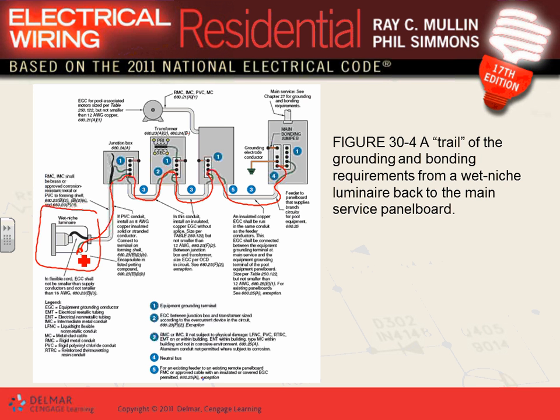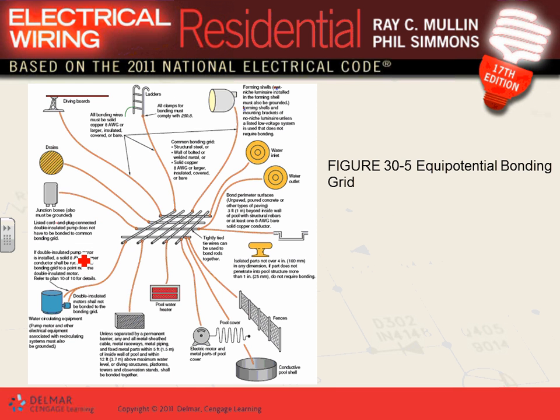We have an isolation transformer that they use for some of these systems. So when it comes to wiring a lot of the electrical equipment, there are tons of number 8 conductors bonding everything else. There's a lot of equipment and conductor, more than normal, to make sure that the system is properly grounded. So that's a good example of what we do more of when it comes to the swimming pool. And we'll look at these in a second.